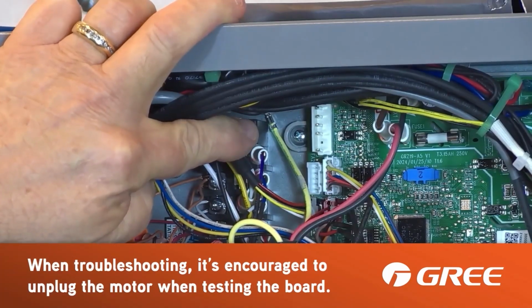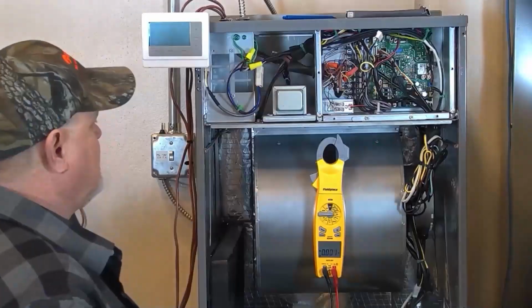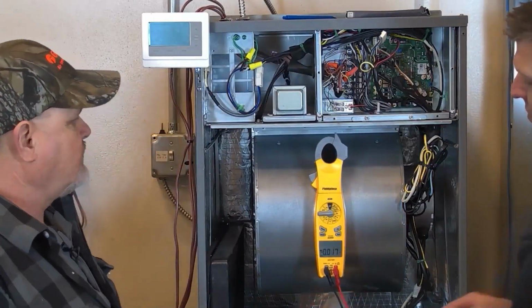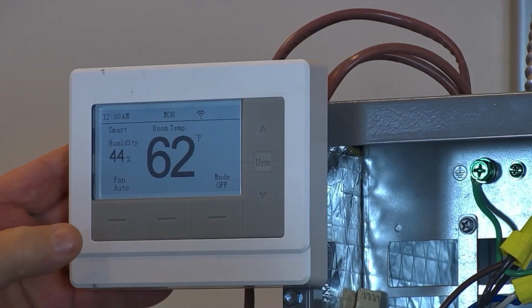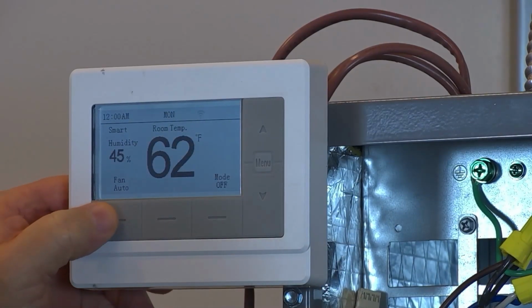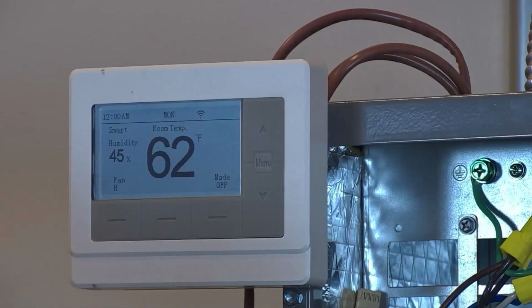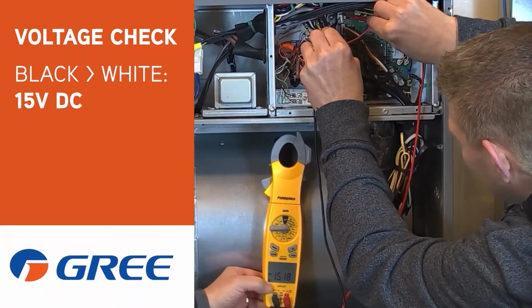We're going to power this up and get the meter leads in there for a voltage test. Give it a brand new call — let me give it a fan call. All right, you've got a high-speed fan call. So, black to white pins — we should have 15 volts DC.